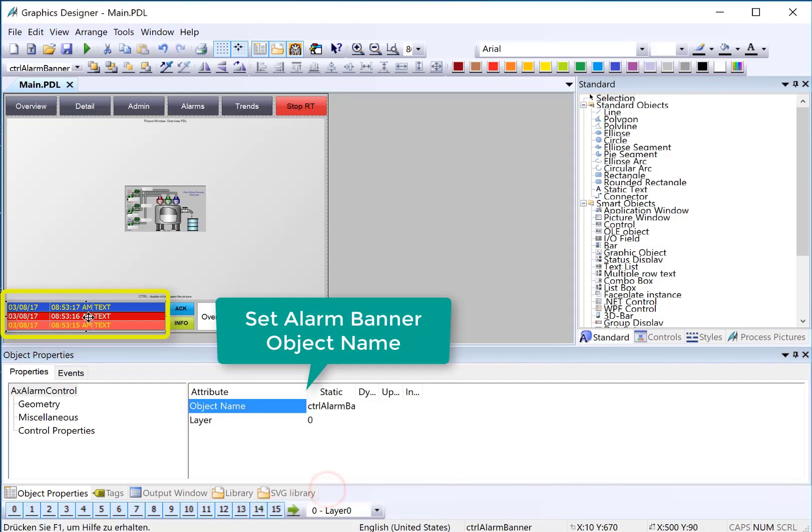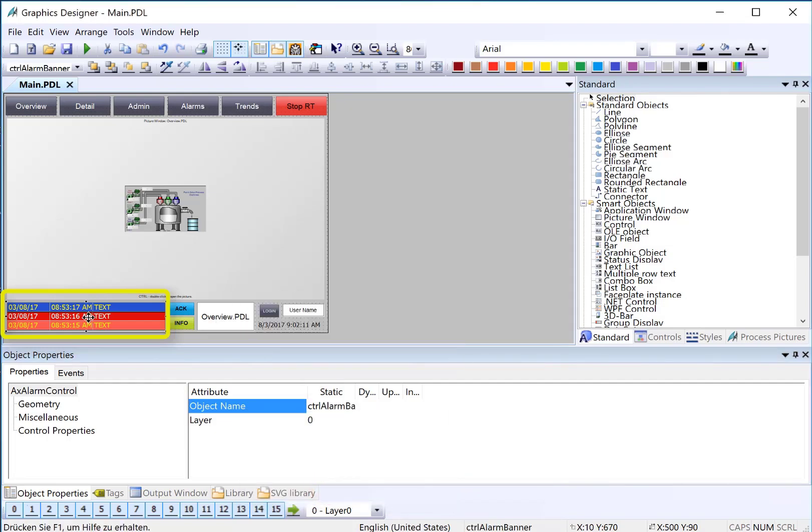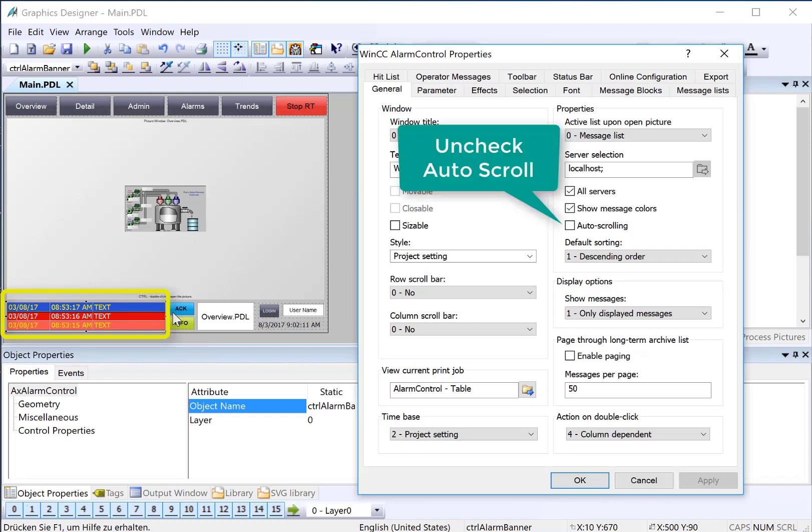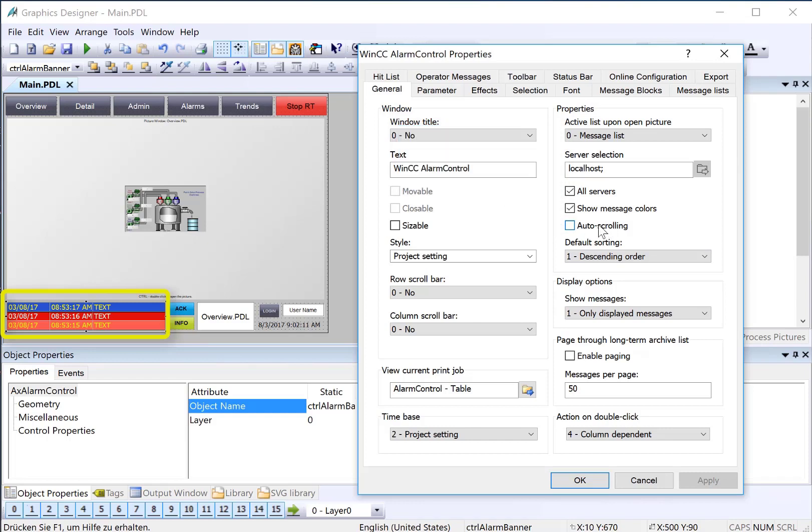Next, let's just take a look at the properties. If we want to acknowledge an alarm that's on this banner, we have to select an alarm. And then we're going to hit Acknowledge. We have to duplicate the single acknowledgement functionality on the toolbar. The first thing that we have to do is make sure that auto-scrolling is unchecked. That allows you to make selections of individual alarms on the control.